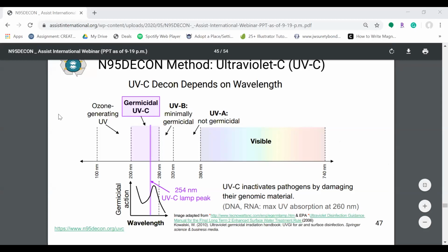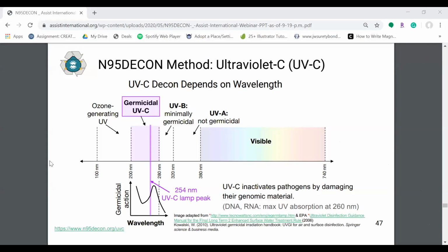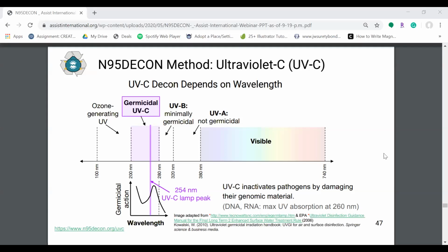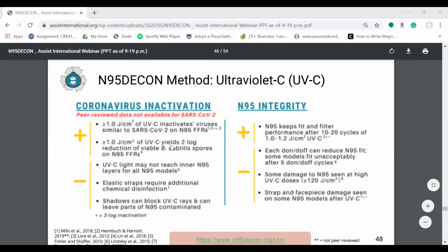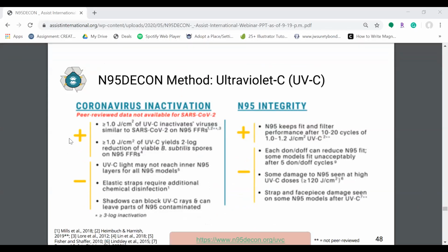But this is sort of what we're talking about when we say UVC light. This is the range you need to be in for it to be effective. You can see UVA here, UVB here. Those are both valuable for other purposes, but they're not germicidal. You have to hit this peak in the range between 200 nanometers and 280 nanometers wavelength. And you also need to provide this much power here. That's 1 joule per centimeter squared of UVC in order to actually inactivate the virus. Anything less than that may or may not kill the virus. It's considered germicidal, but it may or may not affect SARS-CoV-2, the actual COVID-19 virus. And that yields 2 log reduction, just so you know.